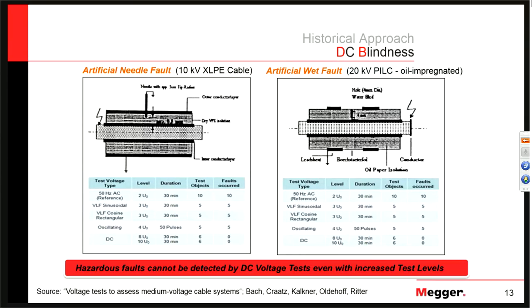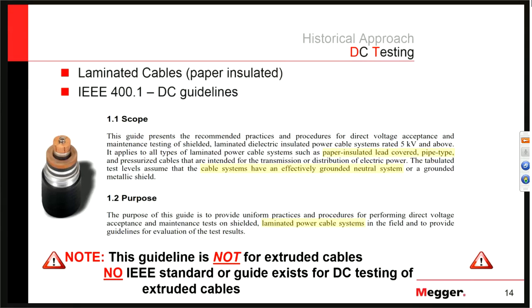Finally, there is no IEEE standard for DC testing on extruded cables. IEEE 400.1 exists, which is DC guidelines for testing on laminated power cable systems — and they go out of their way to specify PILC, paper insulated, lead covered, pipe type, or laminated cable systems. So at the moment, no IEEE standard exists for DC testing on extruded cables.